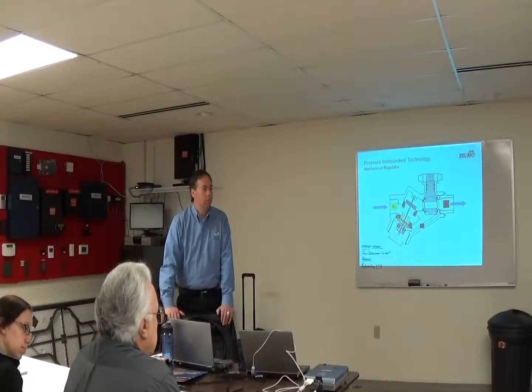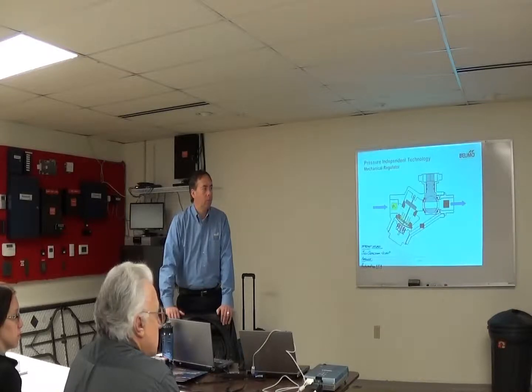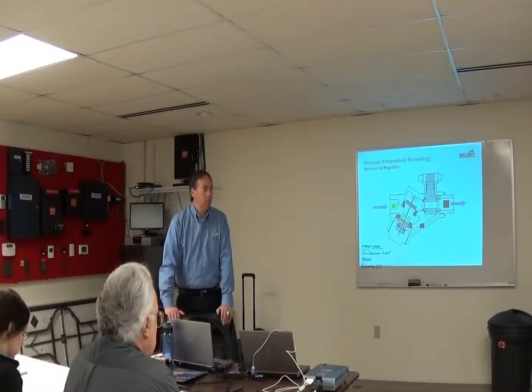You could plug an Ethernet cable in, put it on your LAN, and then you could go to that web address, or that IP address, and you would see the horseshoe-looking pipe that we showed you and the valve in it and all that information. And then you could go in, you get some trending data, there's quite a bit of information, but you can also hook it straight up to BACnet, trend that stuff yourself, do your own graphs, reports.